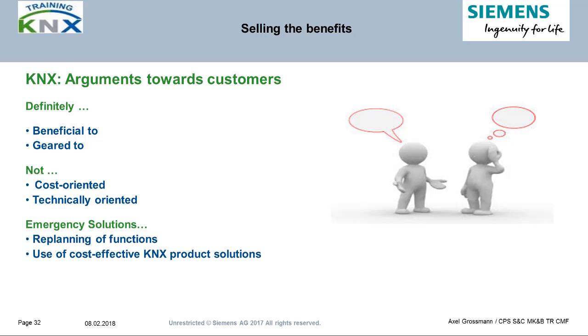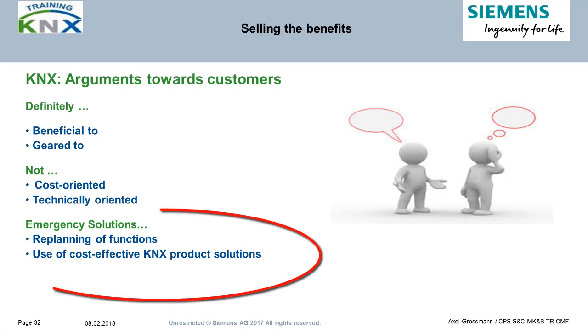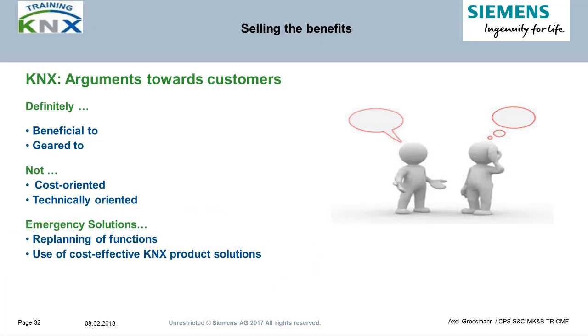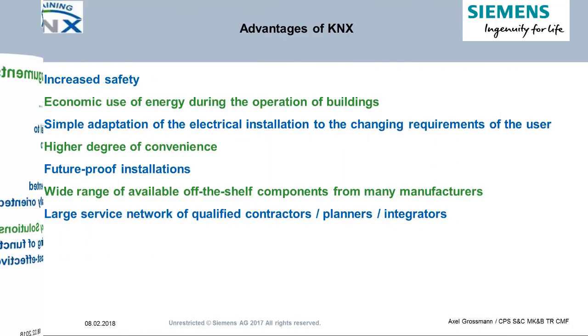Then you have already won the customer for the system, so he only asks if certain features can be realized at a lower price. In this situation, you can offer workarounds, for example actuators with many channels, or redesign of functions, such as switching instead of dimming, or electrical thermal drives instead of motorized valve drives for temperature control.